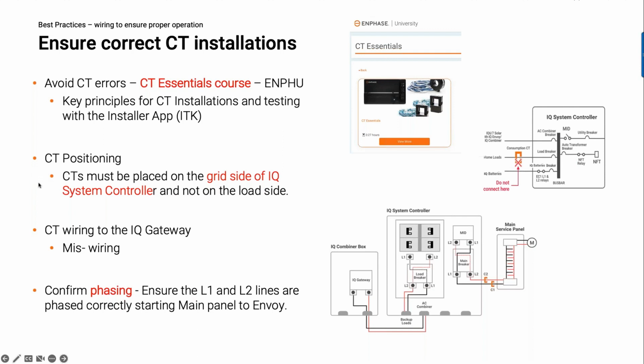Second thing is to be reminded of where to put CTs. There's a specific place to put CTs and a specific place where you shouldn't put CTs. CTs for consumption should always be on the line end and not at the load. So you don't want to put your consumption CTs off of your load breaker. It always should be on the mains on the supply side. If you put them on the load side, you're going to cause the readings to be inaccurate in terms of operating the system. So they must be on the supply side.